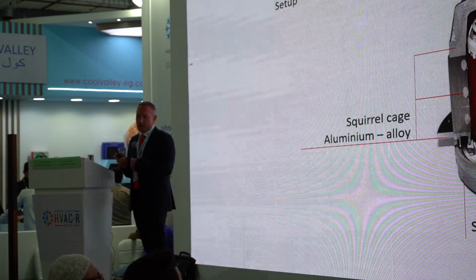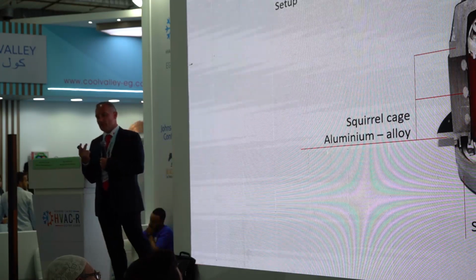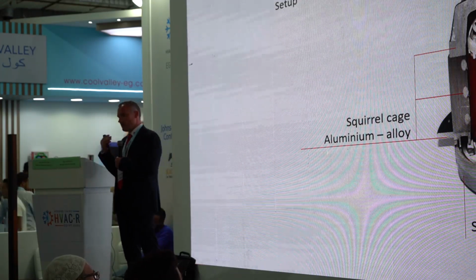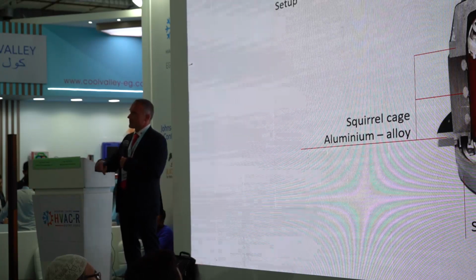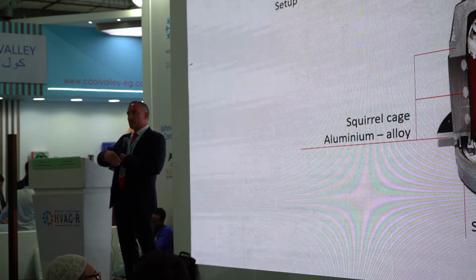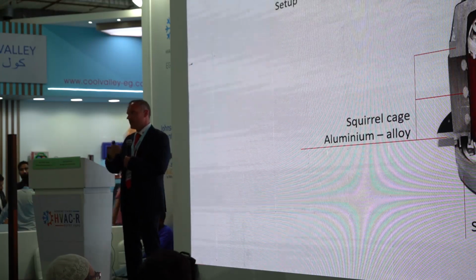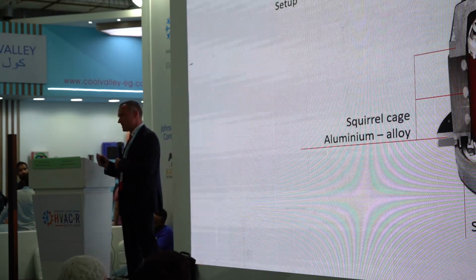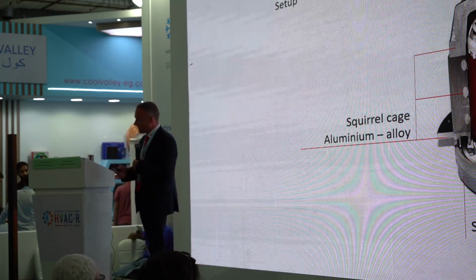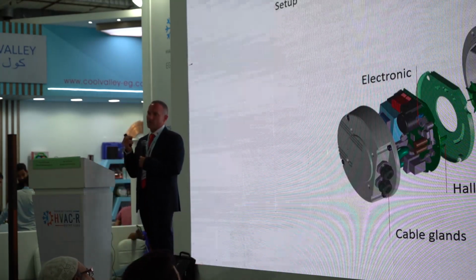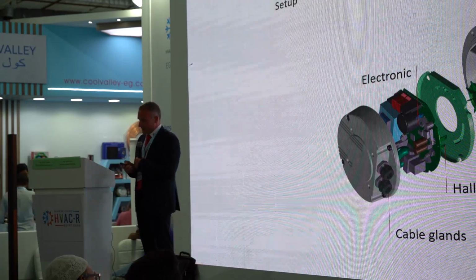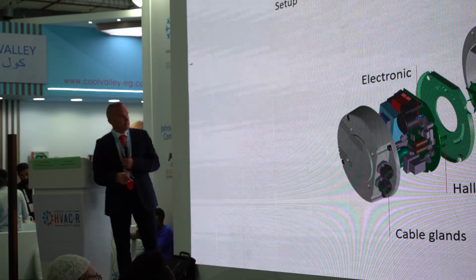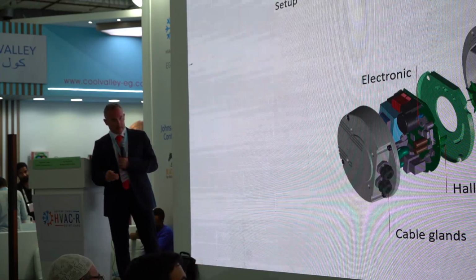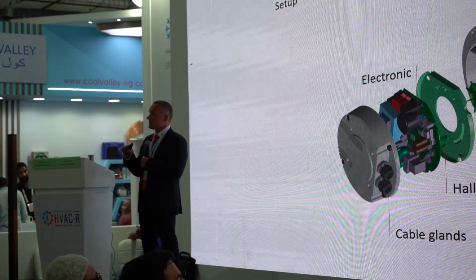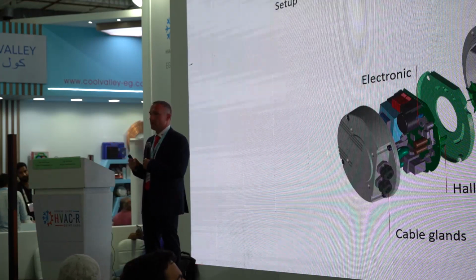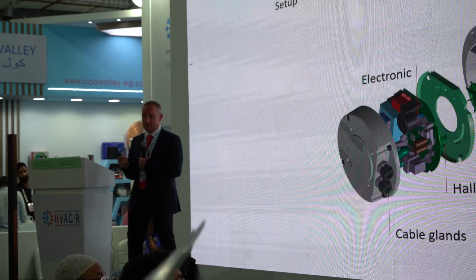Some additional words on the AC motor. The stator has to be powered by current, then the AC motor creates a magnetic field. And if you create something, you need energy. Creating a magnetic field means losses inside the motor. That's the difference to the DC motor, where we have permanent magnets. Here the electronic gets the signal, the 0 to 10 volt signal, or if available a Modbus signal, which can also be handled by the electronics.